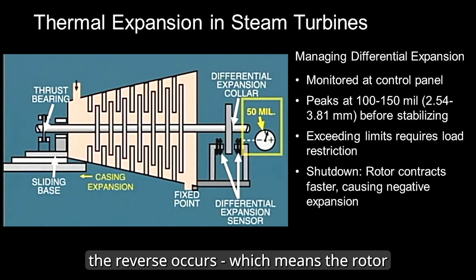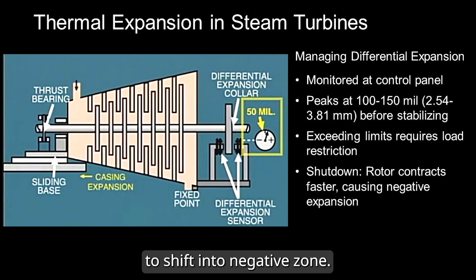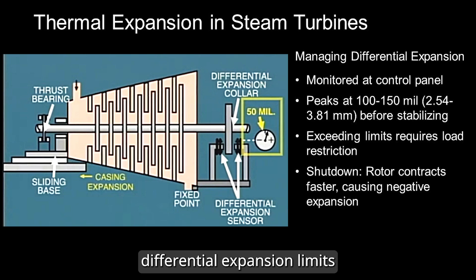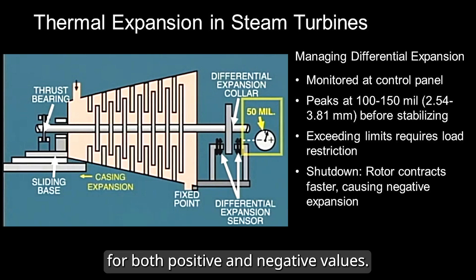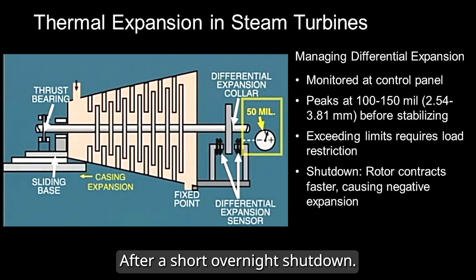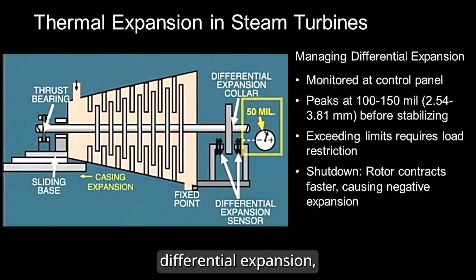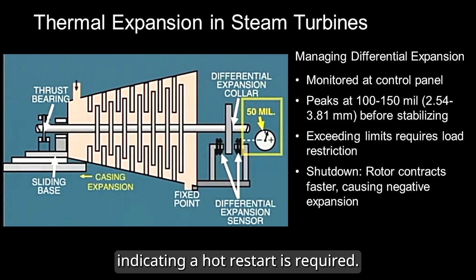During shutdown, the reverse occurs — the rotor contracts faster than the casing. This causes differential expansion to shift into a negative zone. Manufacturers specify safe differential expansion limits for both positive and negative values. The governor pedestal's expansion position is also monitored. After a short overnight shutdown, the rotor contracts faster than the casing, leading to negative differential expansion, indicating a hot restart is required.